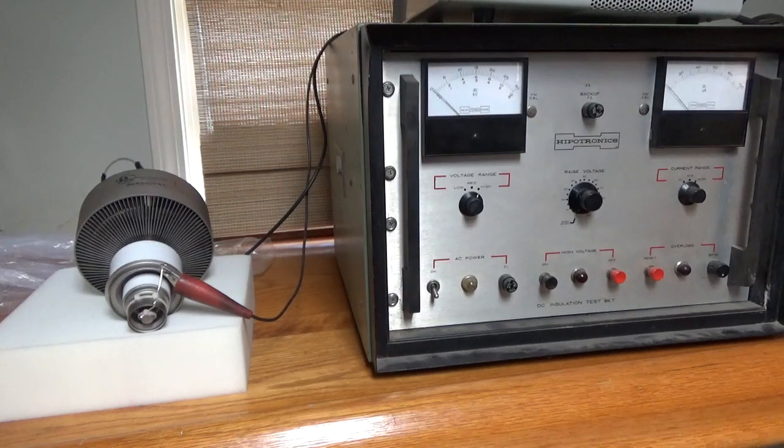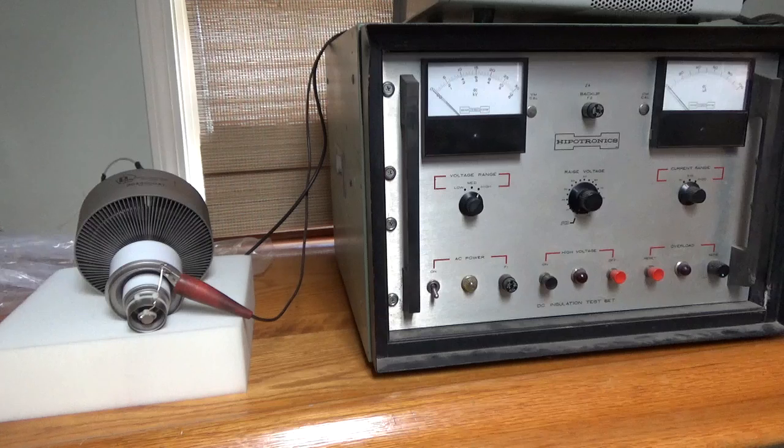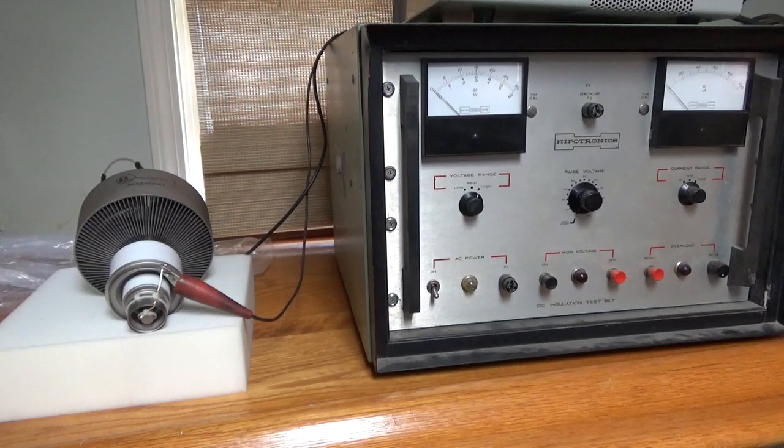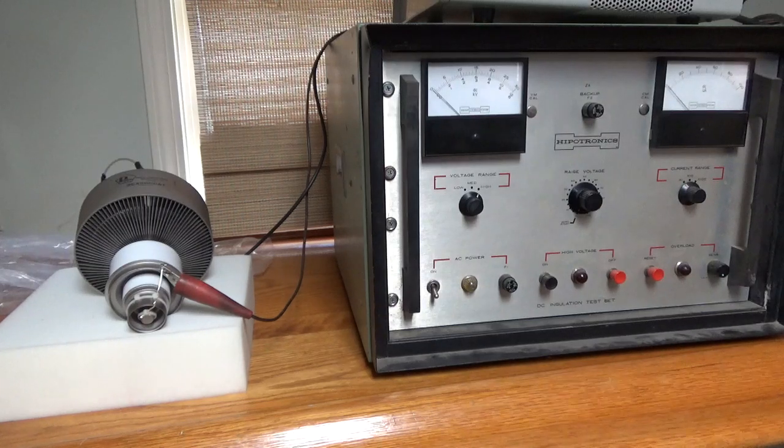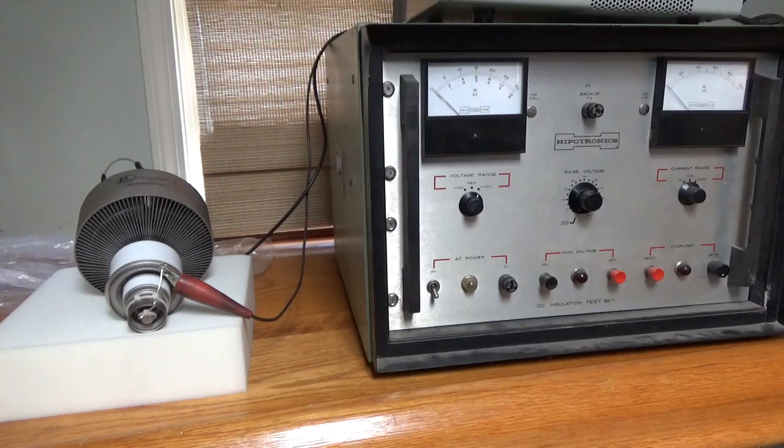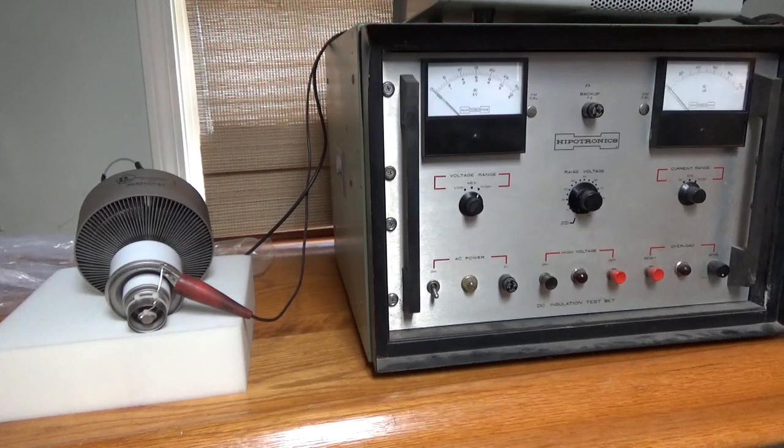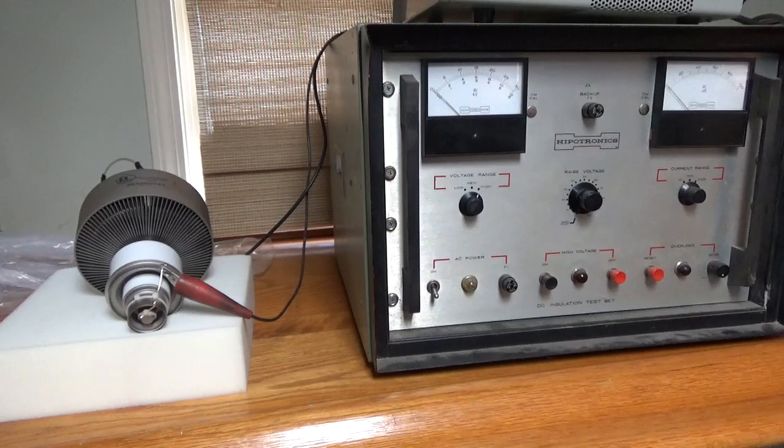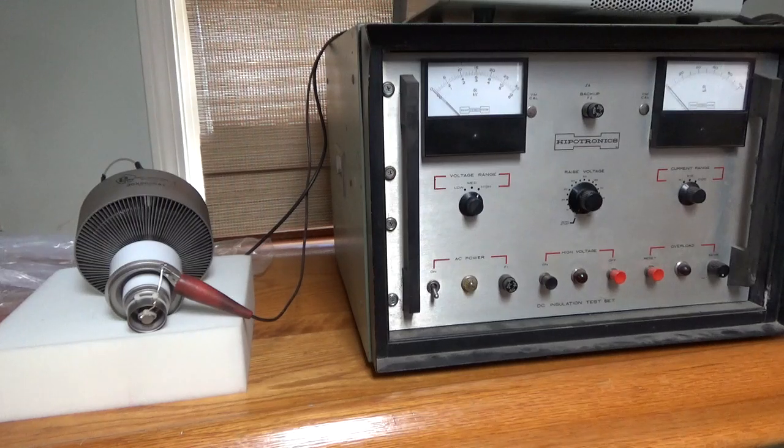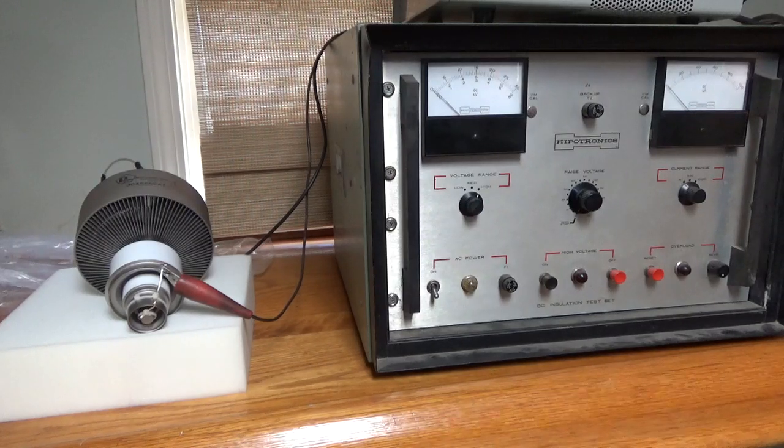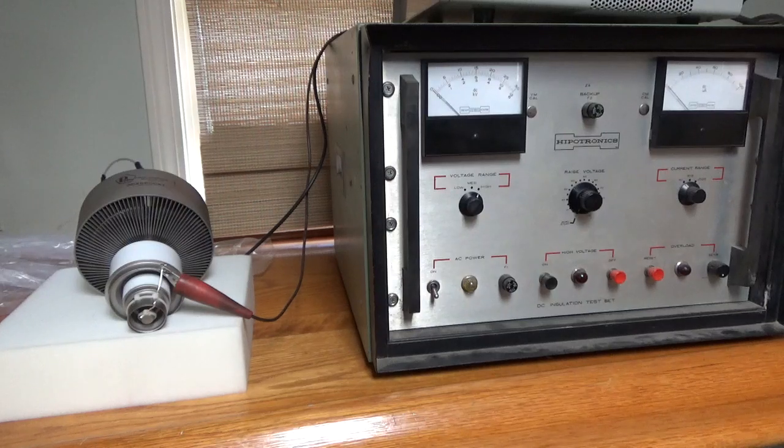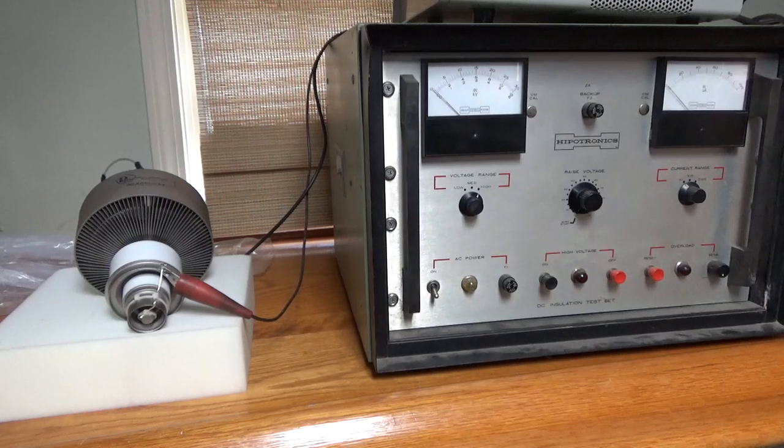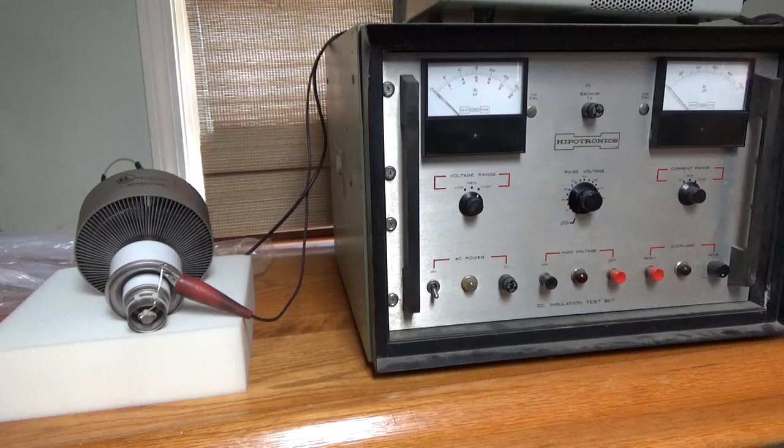Okay, so today we're going to high pot the Pentalabs 3CX6000A7. It's a brand new tube. I always high pot tubes just in case something could have happened during shipping. I have no control over the shipper, so I don't know how they handle things. FedEx usually does a really good job, but I always rather be safe than sorry.